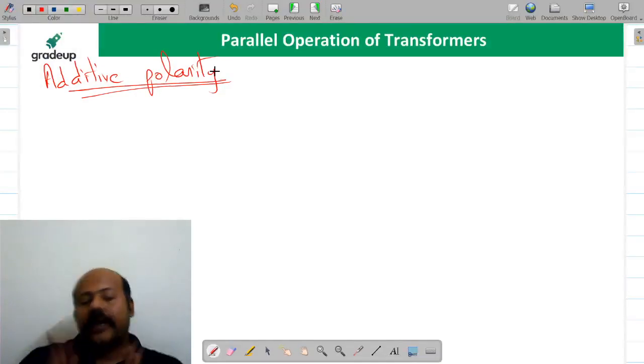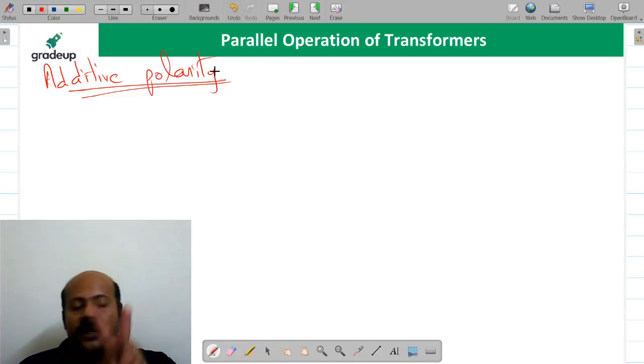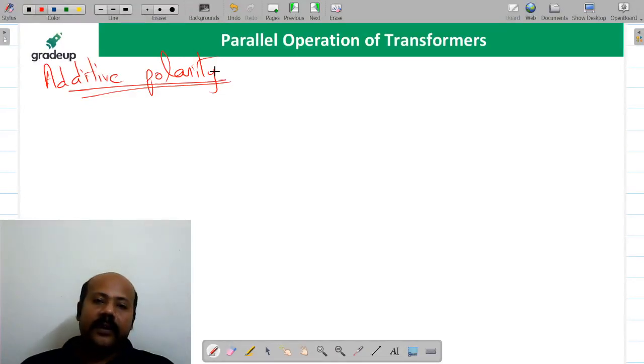Now please try to understand, whenever you have two inductive coils, for example for a two winding transformer, one for the primary side and one for the secondary side, you reconnect those windings to form an autotransformer. There are different ways to reconnect the windings, and you have to consider two cases: first, with additive polarity, second, with subtractive polarity. So we'll see first the additive polarity. If you are following the additive polarity, see what is going to happen.